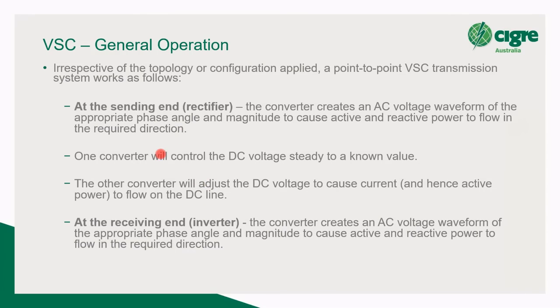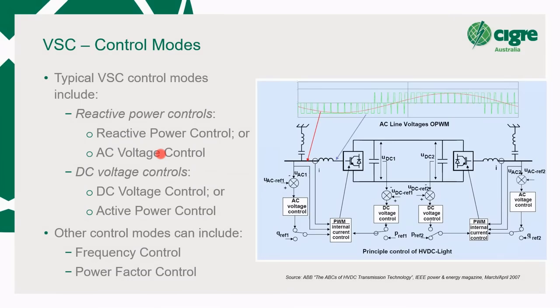At a selected end, one converter will hold the DC voltage steady to a known value. The other converter will adjust the DC voltage to cause current to flow one way or the other across the line. And then at the inverter end, the inverter creates an AC voltage waveform of the appropriate phase angle and magnitude to cause active power to flow in the other direction. So you can imagine all three controls need to be perfectly matched to make sure that the amount of power going in the rectifier, across the line, plus losses, comes out through the inverter. And effectively that's how a VSC works, regardless of what the topology is.